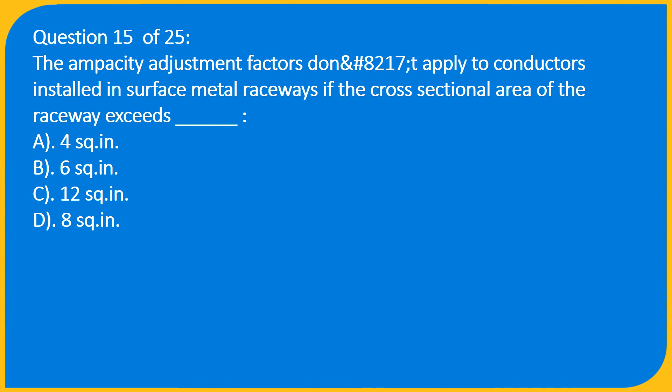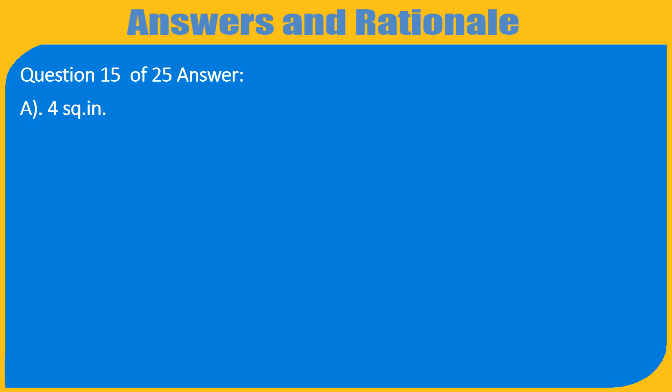Question 15 of 25: The ampacity adjustment factors do not apply to conductors installed in surface metal raceways if the cross-sectional area of the raceway exceeds how many square inches? A. 4 sq. in., B. 6 sq. in., C. 12 sq. in., D. 8 sq. in. Answer: A. 4 sq. in.